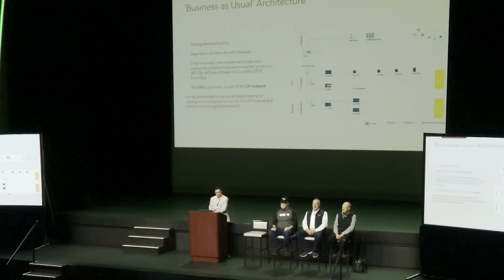The last thing you want to do is do it yourself, and then you turn the building over, and the IT department tells you we're not going to accept that, we have to control it, and you have to redo all the certificates on the site. I think that would be one of the biggest, and then going through the whole learning process of some trial and error, right? If it's your first time, nothing beats having a couple controllers on a bench somewhere, and the guy who's going to implement it start playing and trying to figure out how it works. At least that's how I always learn, right? I got to break it and then fix it before I fully understand it. So those would be where I would start.